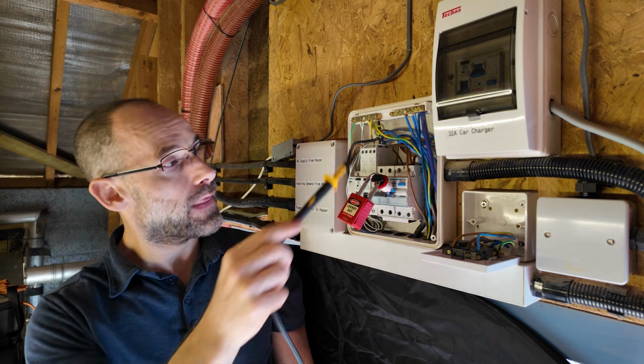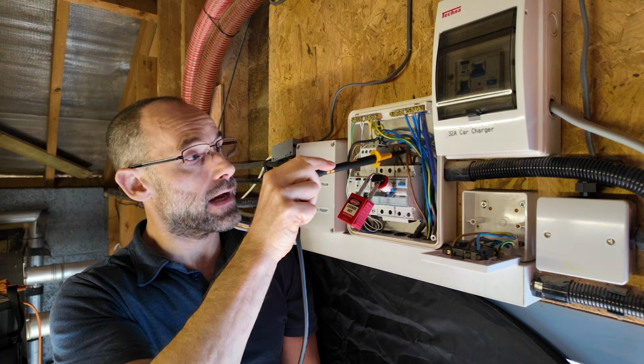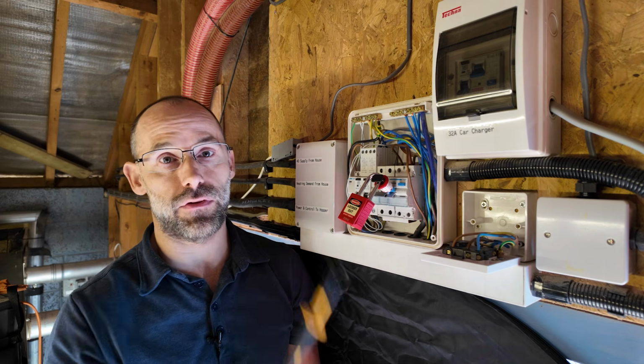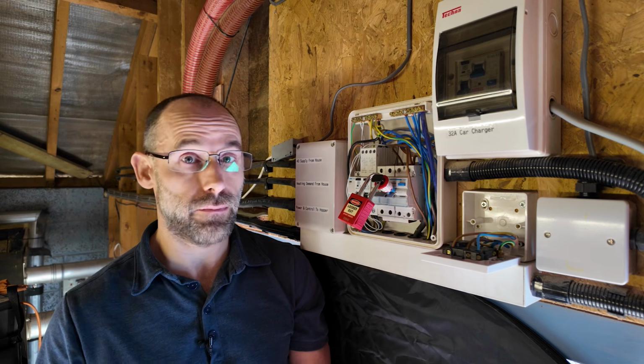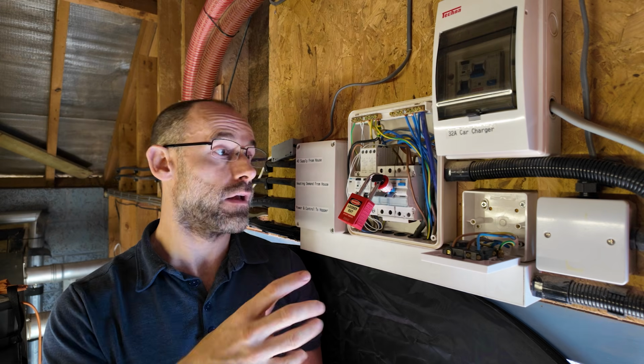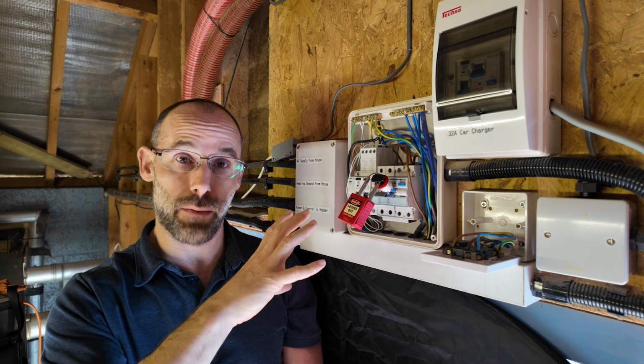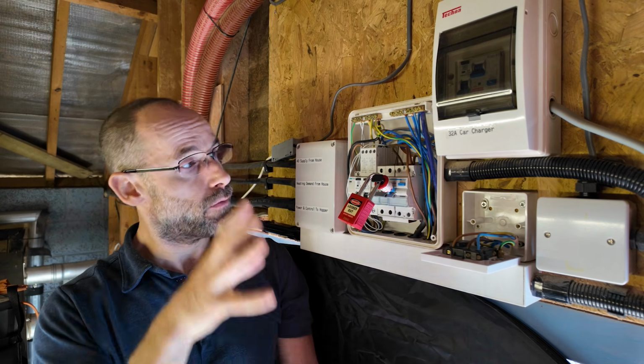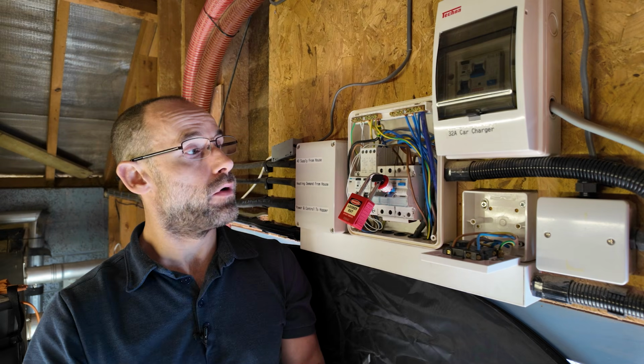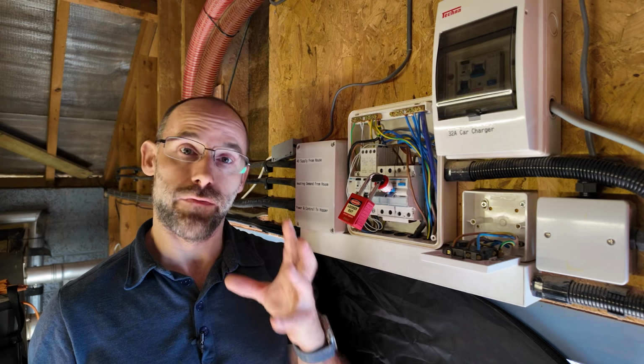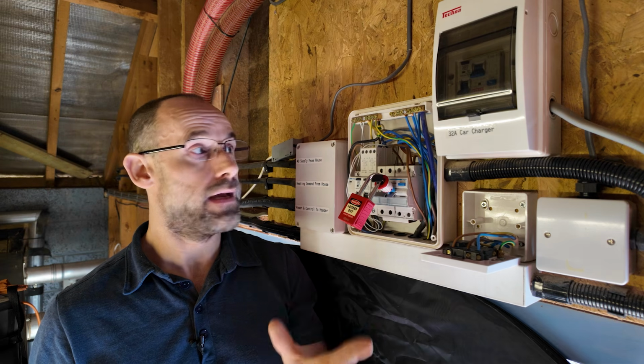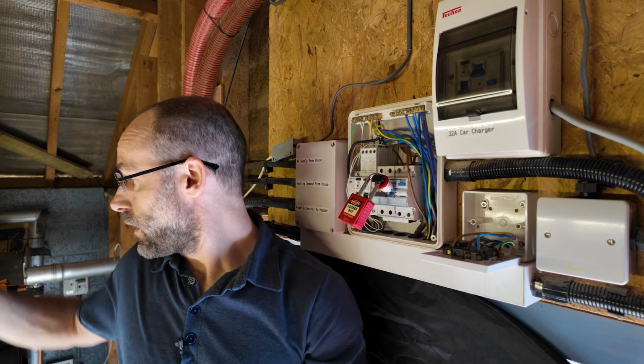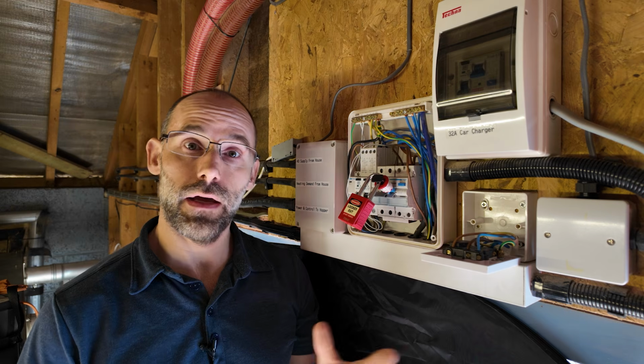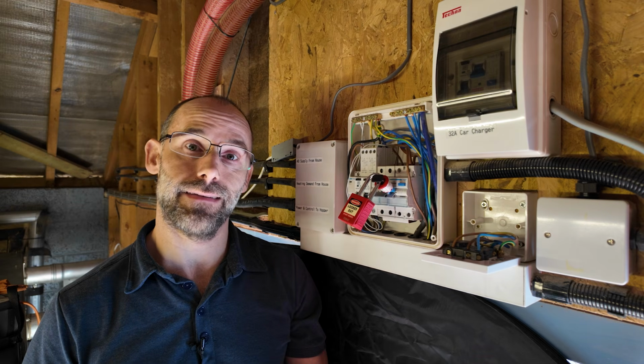Now, if all three of those tests come out as you'd expect, then you know that these things are correct, right? Because just because this is a blue cable and this is brown or whatever the colors are in your country, doesn't mean somebody's connected it properly the other end. So we're here, this is our focus, this is a sub board, there are other boards upstream, but we're focused on this, and now we know that these cables are the voltages that we would expect them to be, and they're identified correctly. So that's that. That is something called live polarity. Lets us move on to the next test.